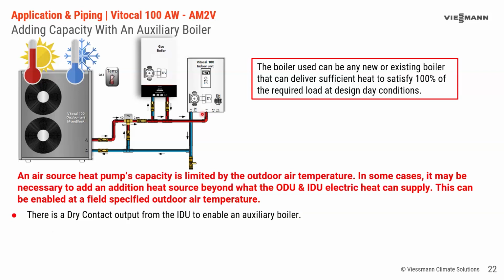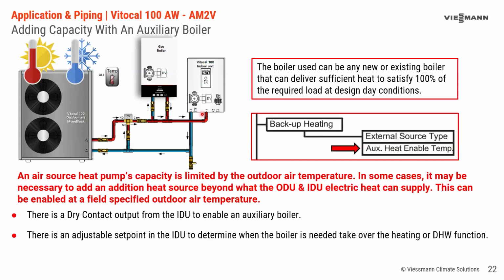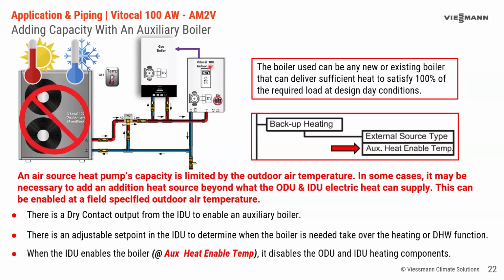And there's an adjustable set point in the indoor unit called auxiliary heat enable temp, which will be the point at which we're going to say, in this installation, wherever I am in North America, in Fort McMurray, Alberta, or Minnesota, or Texas, you're going to have a point where you may need the heat augmentation because the heat pump can't move energy at that certain outdoor temperature. So when this point is enabled, the indoor unit sends a signal to the boiler, says, hey, you're in charge now. You're doing the heat. We're not giving it a set point. The set point is coming from the boiler itself. So you're going to have to set the set point in this boiler for the design temperature you need.